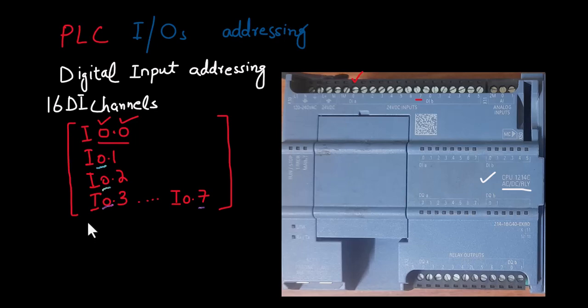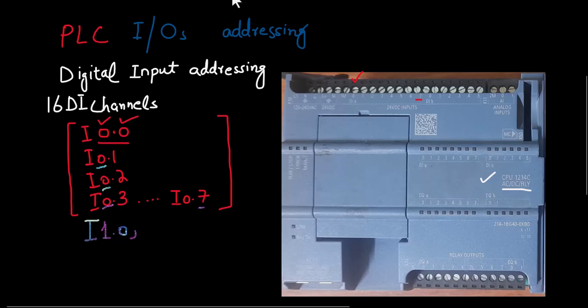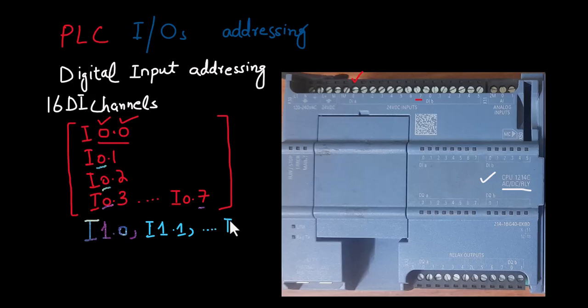So byte address 0 will accommodate eight input channels. Once we start again, we have six additional digital inputs. To refer to those additional inputs, we will start from byte 1: I1.0, I1.1, and all the way to I1.5. So six digital input channels have been addressed starting from I1.0 and ending at I1.5. This is how we refer to the digital input channels in our PLC program.